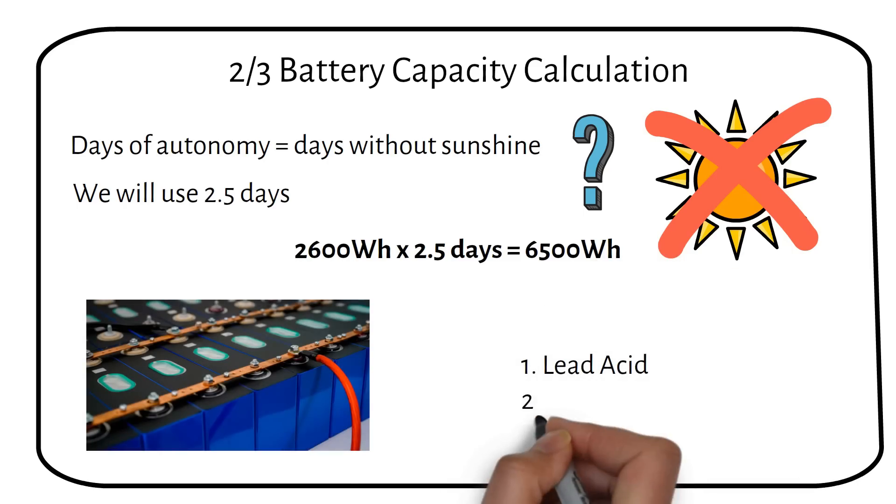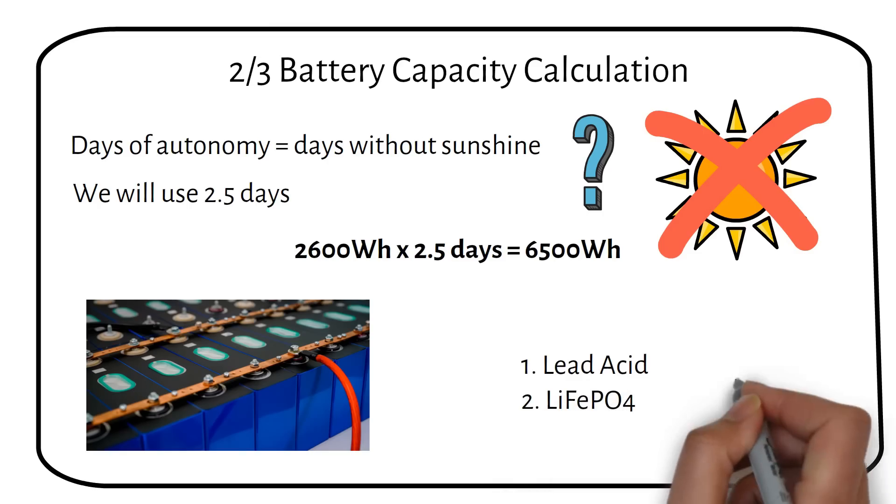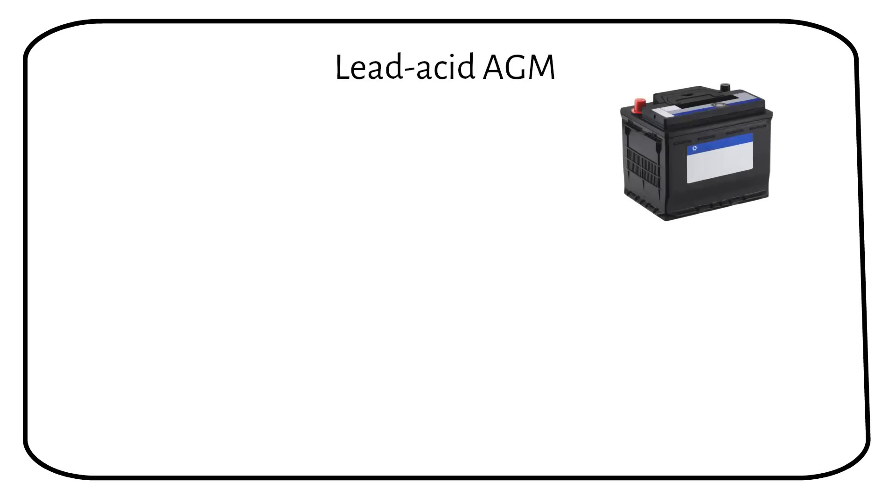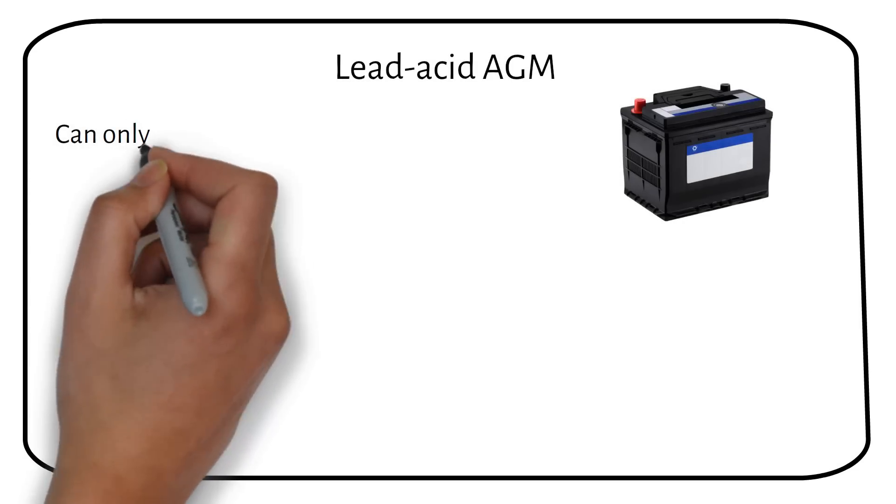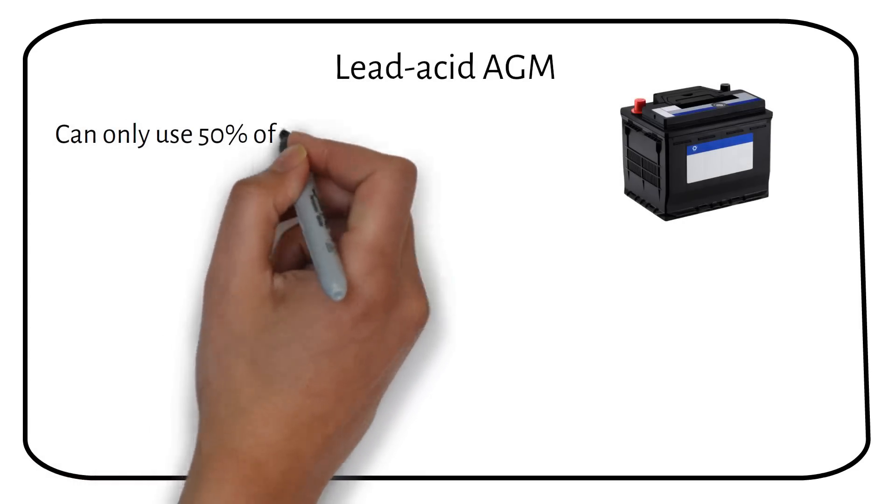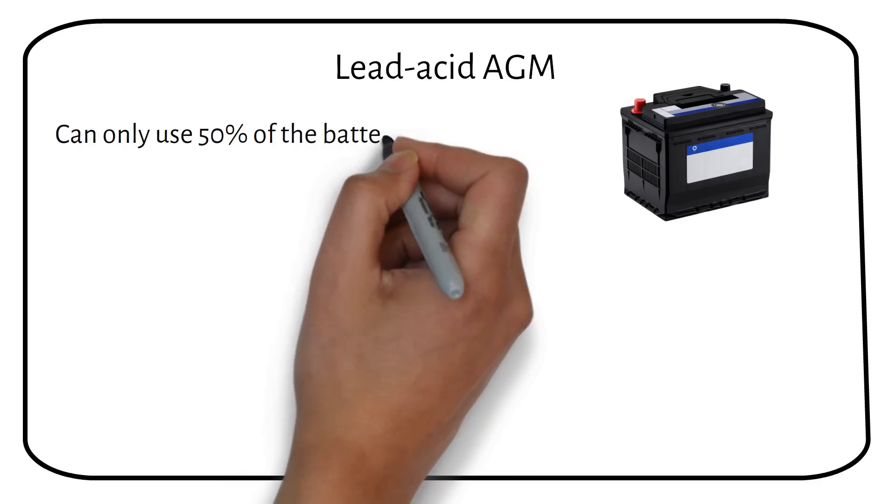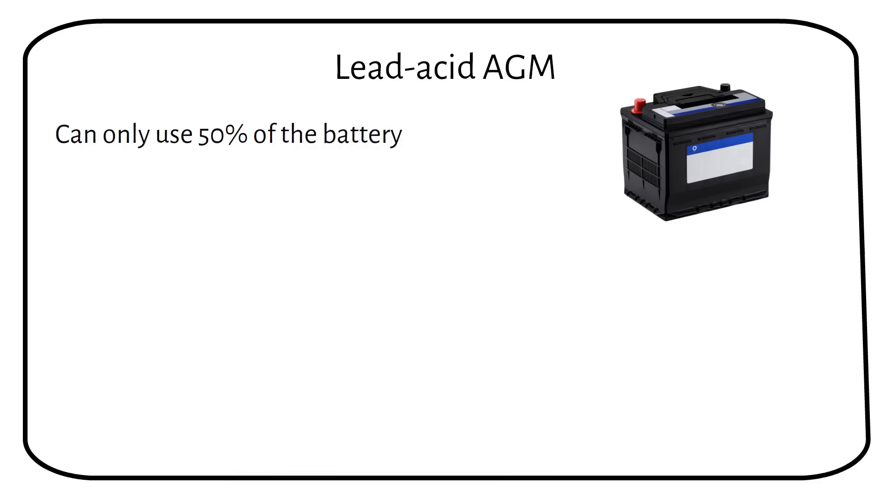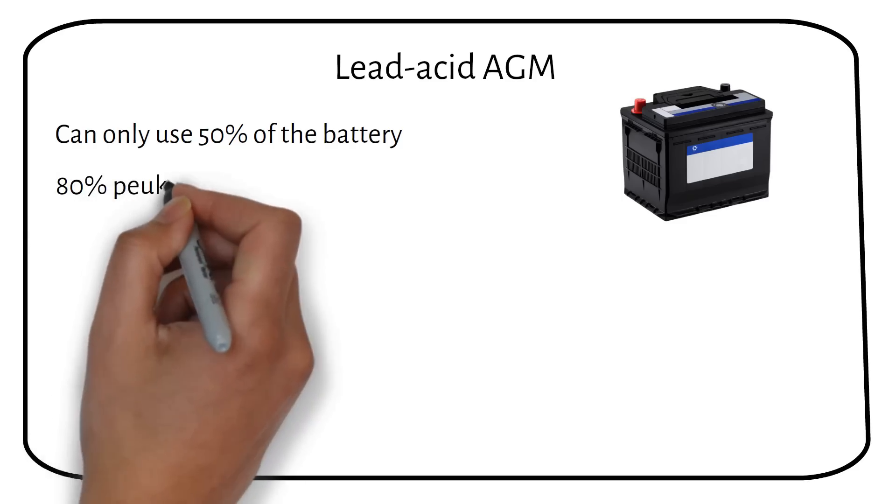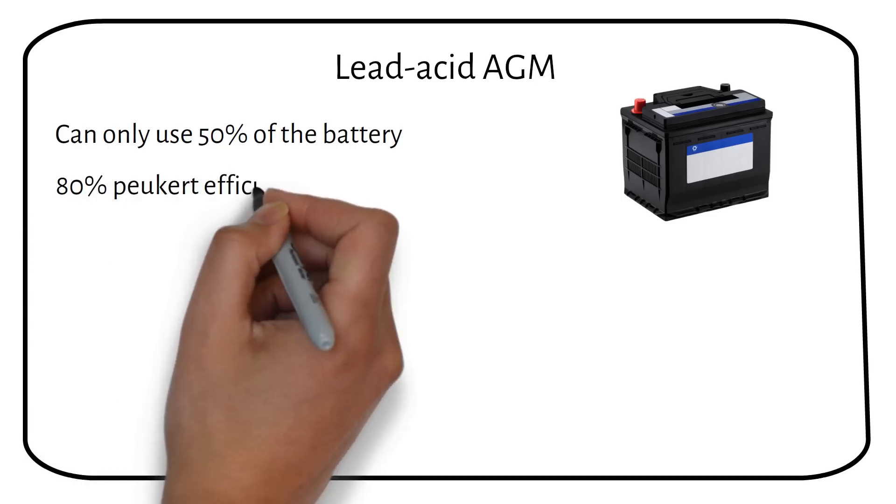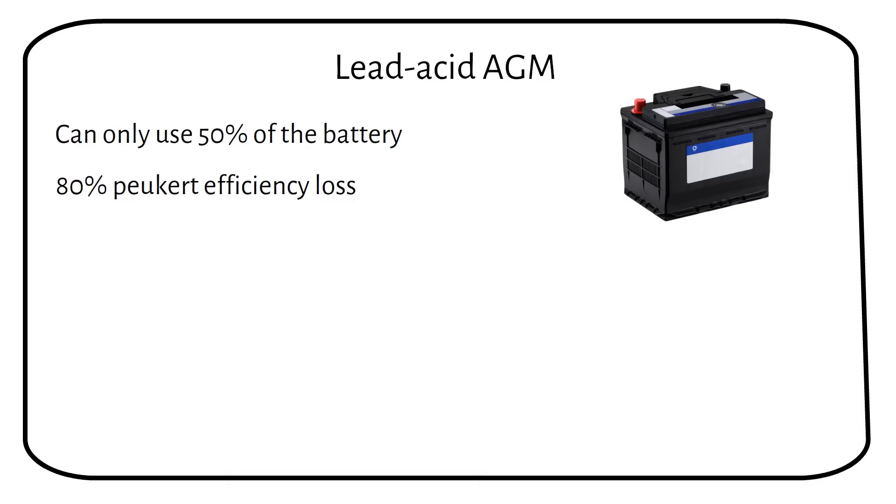Now I'll make a calculation for lead-acid batteries and lithium batteries. Because both will be different. If we use a lead-acid battery, we can only use 50% of the capacity. So we must double the capacity. The first half will stay in the battery. The other half will be charged and discharged. So it's subject to the Peukert effect, which is the losses through heat generation at different currents when charging and discharging a battery.